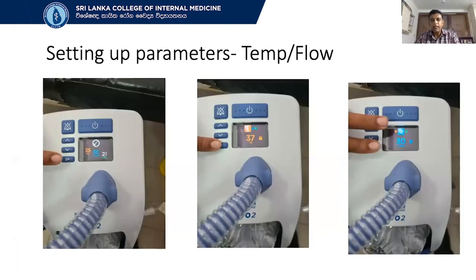And there are 3 parameters that we need to adjust. It's very easy, but you need to know them. On your left screen, you have the 3 parameters: temperature, flow rate, and FiO2. On your middle screen, you have the temperature. You can set it from 32 to 37. Usually we set it at 37 for it to be comfortable. But if the patient complains, we can bring it down to 34. Then the flow rate. Flow rate also we can adjust. We can start from 10. We can work ourselves up to 60 liters. But be mindful about the flow rates, because of the problem of oxygen consumption. So with very low flow rates, like 15 liters, you can achieve your target. So then it won't waste your oxygen.